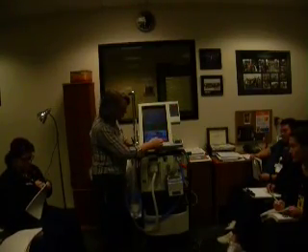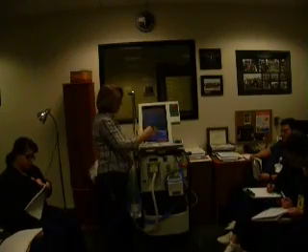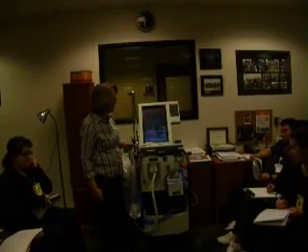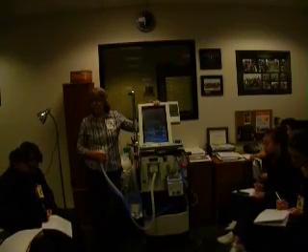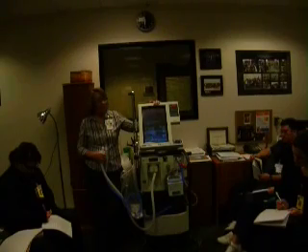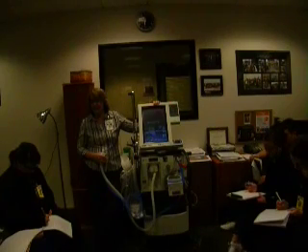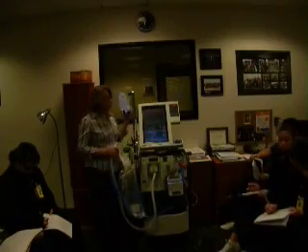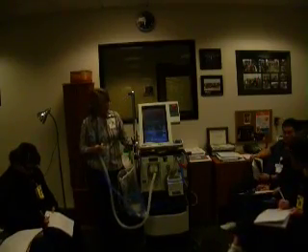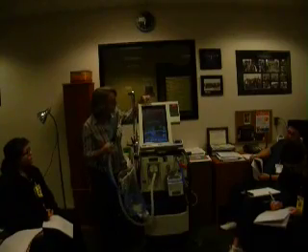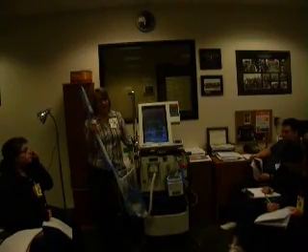Then you'll see it says use knob to adjust, to apply, press accept. So now I'm going to hit accept because I put everything here the way I want it to be. We'll just pretend that I did. So now I hit accept. Now notice the top says waiting for patient connect. I've now set my settings and confirmed them, so the ventilator is now okay with me hooking it up to my patient. Not before this time, because in the ventilator's mind you hadn't set it. So you can't be hooking it up to a patient. As soon as you hook it up, it will start ventilating all on its own. And you'll see that that goes away. It senses that the patient was hooked up.